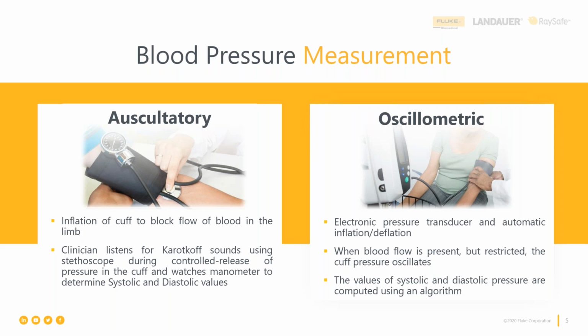Because here's the other thing you've got to understand. Human physiology is quite variable. From moment to moment, your blood pressure is different. It's different from one limb than another limb. So if I'm having my automated blood pressure device on my left arm and I'm trying to auscultate a reading on my right arm, those are two completely different readings, two completely different measurements, and they will produce two completely different values. And they are not appropriate to compare one against the other. They're not apples to apples at all, not in any way.